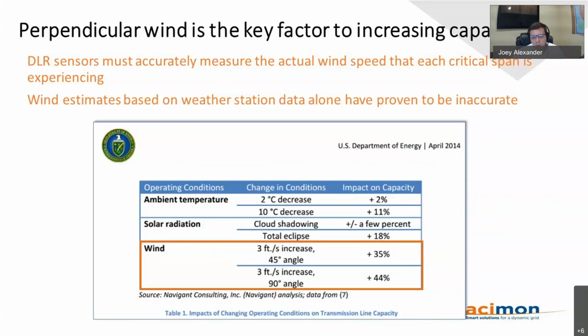Wind is one of several environmental variables used in all the different standards-based dynamic line rating models. If you get wind wrong and overestimate it, you're at risk of rating your line way too high, which could be an unsafe condition. So making sure you have a really good handle on that wind speed, measuring it as it impacts the line, is extremely important.